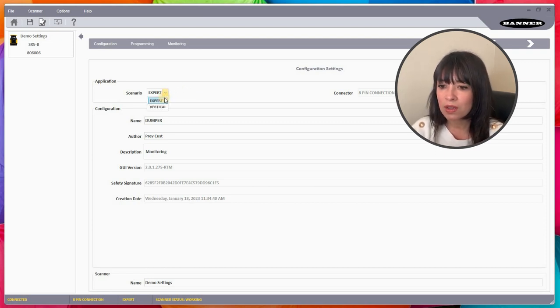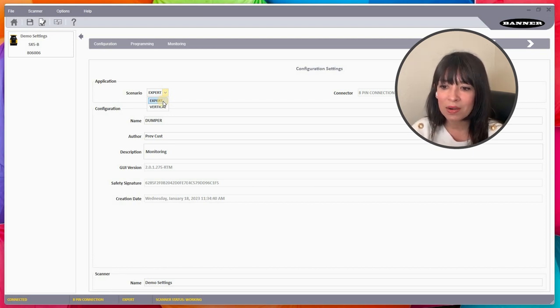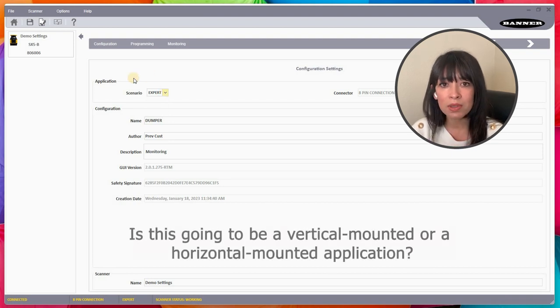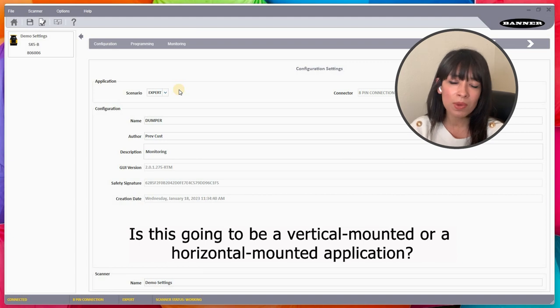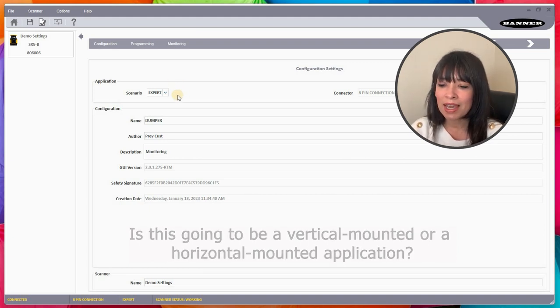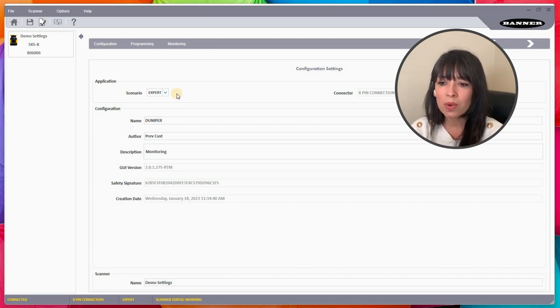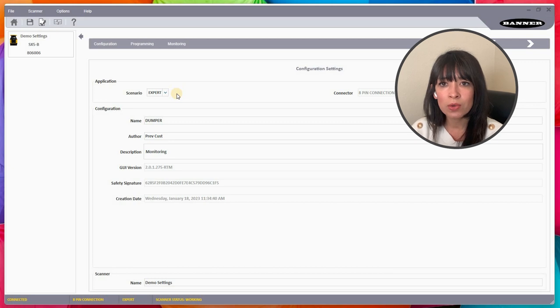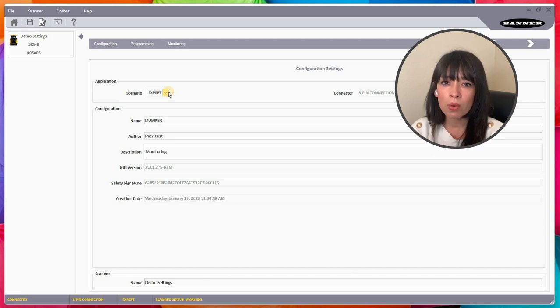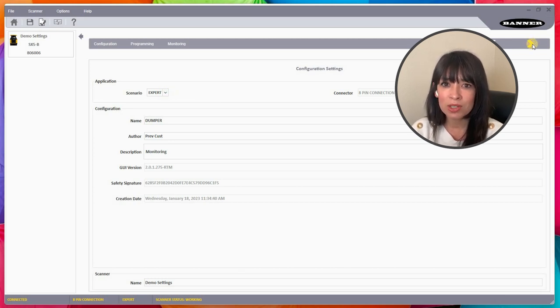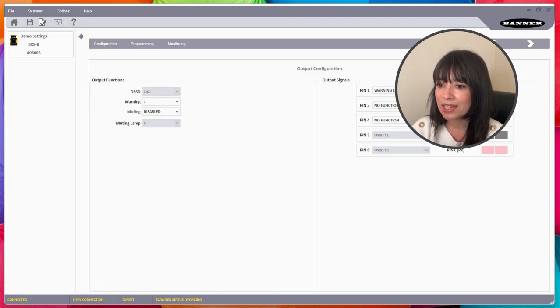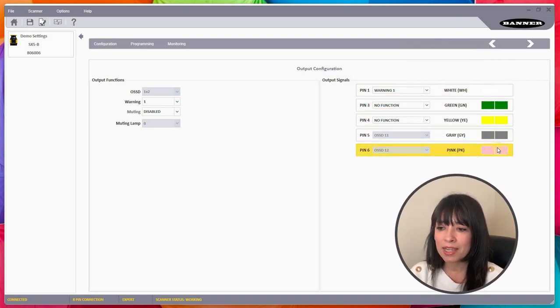For example, number one: Application Scenario. What this is asking you is, is this going to be a vertical application or a horizontal application? We call it Expert. The reason they're asking you that is because if you are doing a horizontal or vertical application, for vertical mounting OSHA actually regulates that specifically. You have to have reference points in there, so the software will take care of incorporating that into your application as you commission this device. That's kind of nice. We have those built-in features.